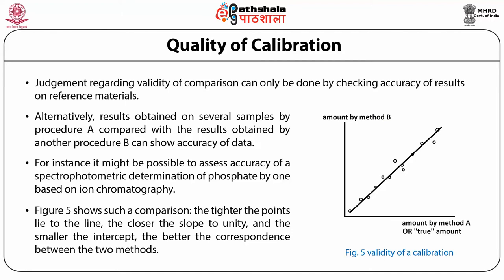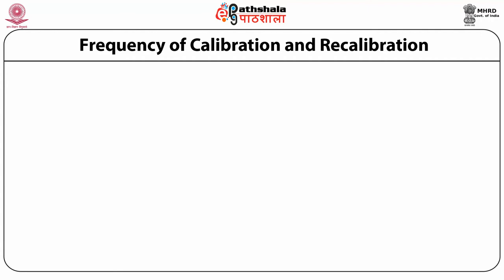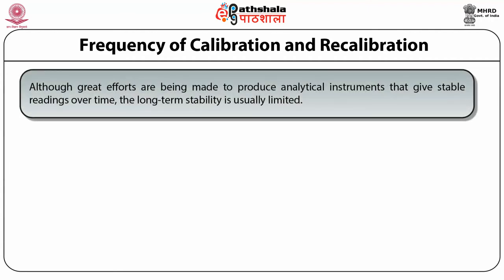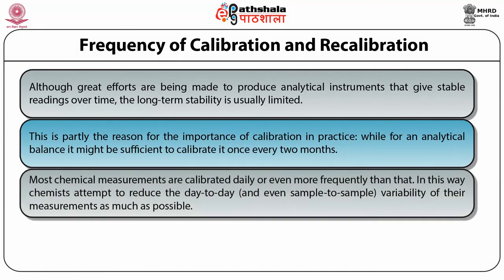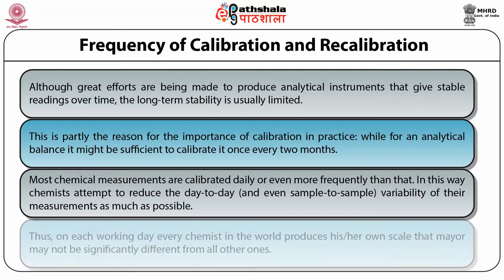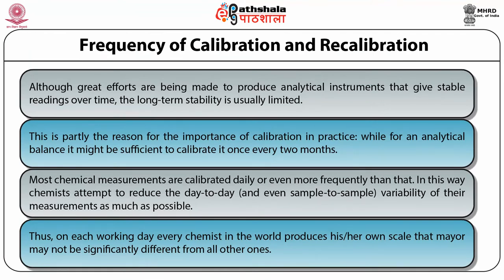The curve is commonly called the recovery function curve. Regarding frequency of calibration and recalibration: although great efforts are being made to produce analytical instruments that give stable readings over time, long-term stability is usually limited. This is partly the reason for the importance of calibration in practice. While for an analytical balance it might be sufficient to calibrate it once every two months, most chemical instrument measurements are calibrated daily or even more frequently. In this way, chemists attempt to reduce the day-to-day variability of their measurements as much as possible.